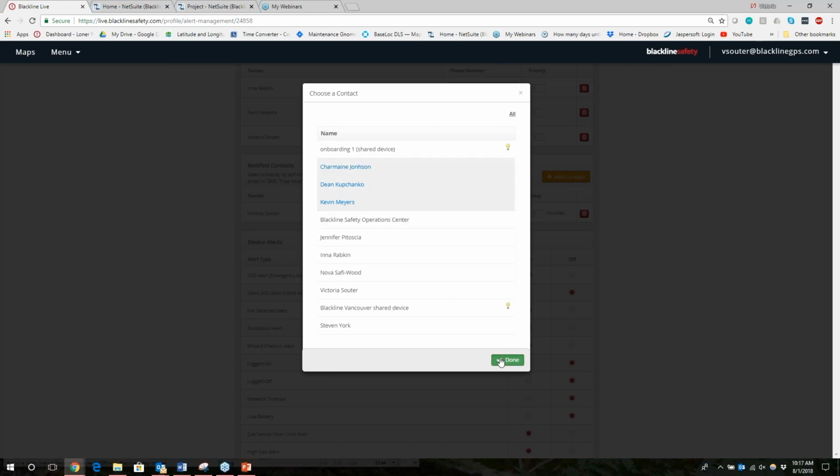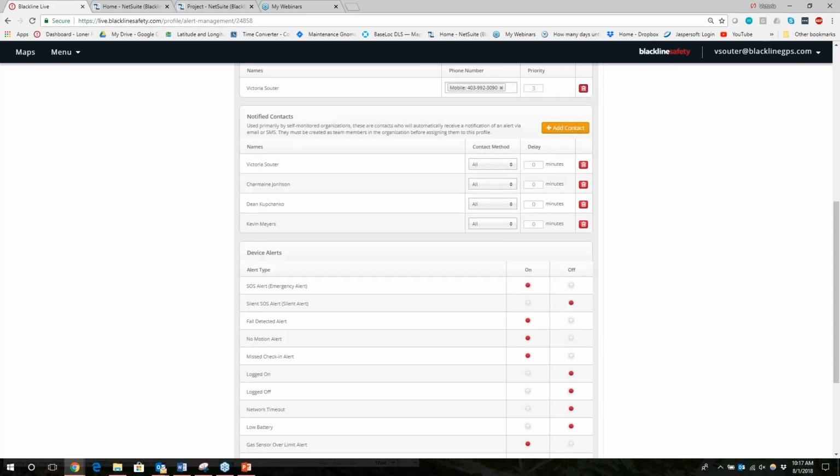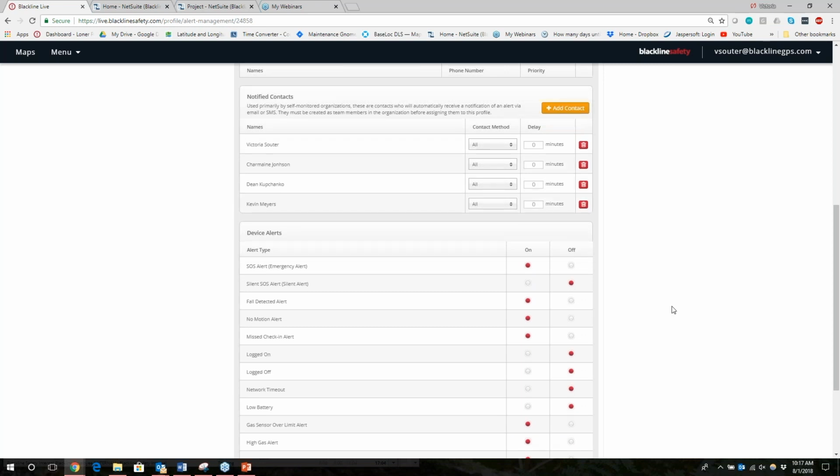So I'm going to put way more names there in the field. Maybe I don't have any people to call because we know who we're calling. We don't need to see the numbers. We know exactly what to do. And then I'll have everyone listed as a notified contact. Now, this is when it gets interesting with self-monitored customers. So everyone is at a 0-minute delay. This means that everyone is going to receive an email and a text the minute that device goes into a high alarm. Great, that's exactly what we want.